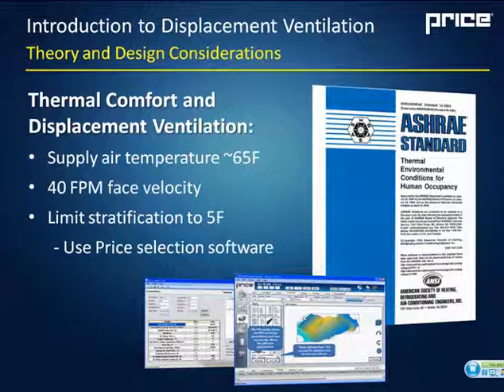The other point is the velocity is significantly reduced. 40 feet per minute is barely perceptible. You can really have your hand up to these diffusers and move it 2 to 3 inches away, and you really don't feel any velocity. So with those two things in mind, you can still maintain comfort for pretty well anyone in the room, as long as you maintain these two guidelines: a supply temperature around 65 degrees and a face velocity or room velocity of around 40 feet per minute.